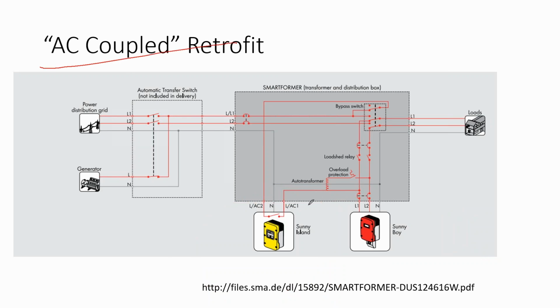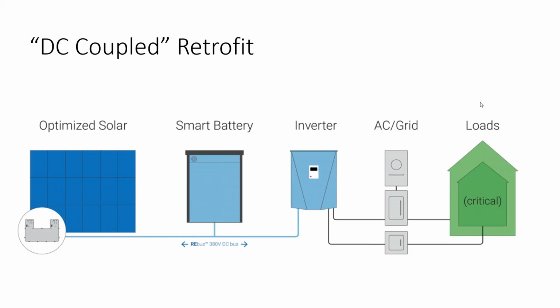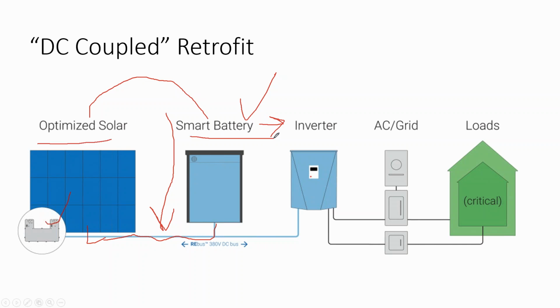So that's AC coupling, when your inverters are located in parallel next to each other. Now there's another configuration called DC coupling. DC coupling is where you have a solar array on a charge controller, and that on the DC side is connected to your battery. So your solar array is connected to the battery before it lands onto the inverter. The solar array and battery are connected to each other on the DC side rather than the AC side. Hence it's DC versus AC coupling.